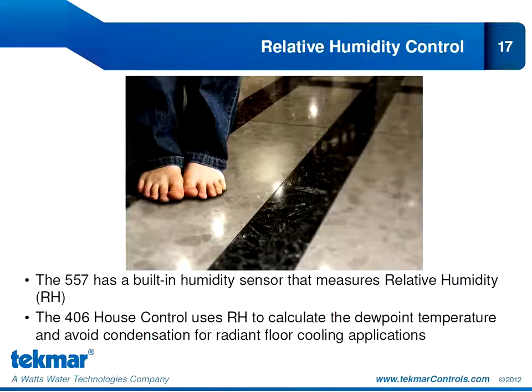For radiant cooling, relative humidity actually takes on great importance because we need to make sure we avoid any risk of condensation. So the 406 will use the relative humidity measurement provided by the 557 to calculate the dew point. And it will reset the water temperature to the floor to make sure we are always at least 2 degrees above the dew point, so we never run the risk of having condensation.